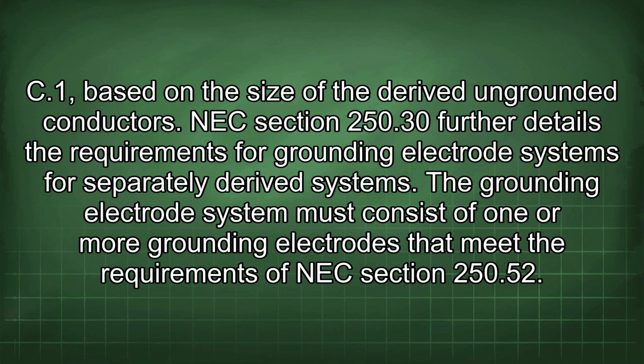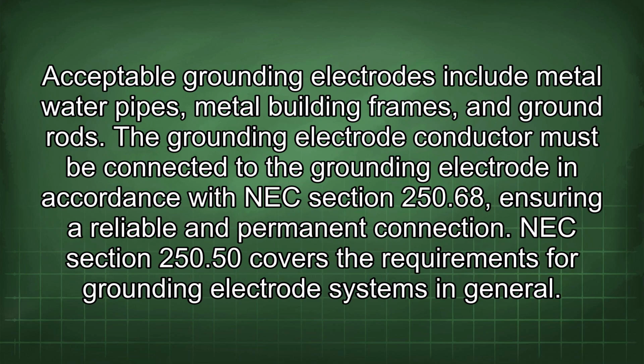NEC section 250.30 further details the requirements for grounding electrode systems for separately derived systems. The grounding electrode system must consist of one or more grounding electrodes that meet the requirements of NEC section 250.52. Acceptable grounding electrodes include metal water pipes, metal building frames, and ground rods. The grounding electrode conductor must be connected to the grounding electrode in accordance with NEC section 250.68, ensuring a reliable and permanent connection. NEC section 250.50 covers the requirements for grounding electrode systems in general.